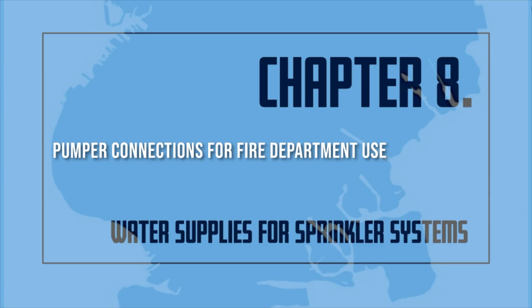Each connection shall be fitted with a lower check valve. The lower check valve prevents the backflow of the private water supply into the fire department connection. The automatic ball drip device between the lower check valve and the outside fire department connection prevents water from building up in the piping and shall be installed in the horizontal position. This ball drip device makes sure that the fire department connection is not blocked by water which has frozen within the piping.